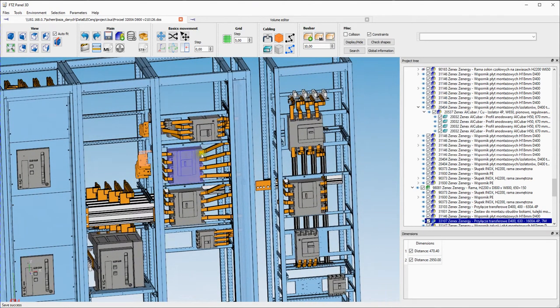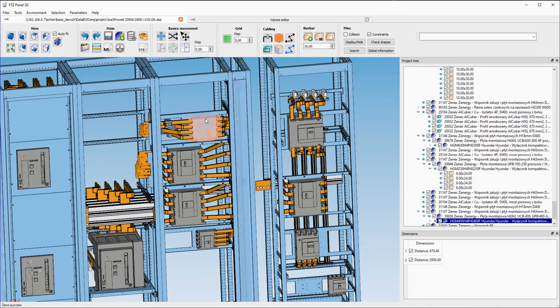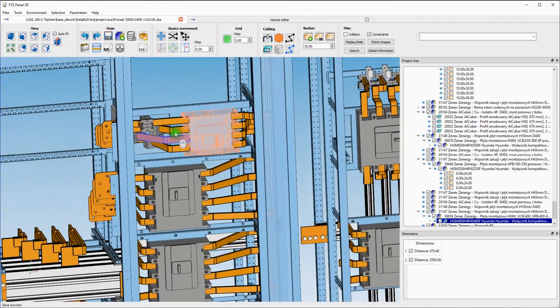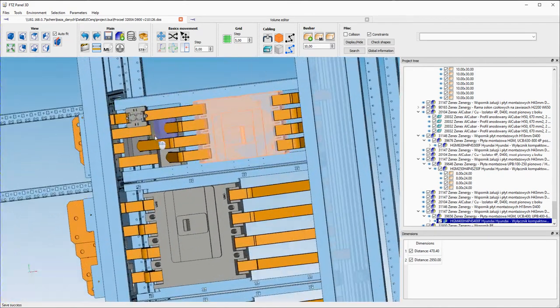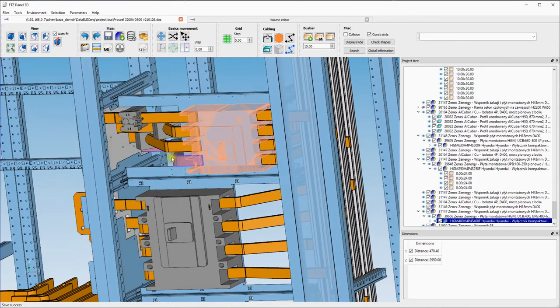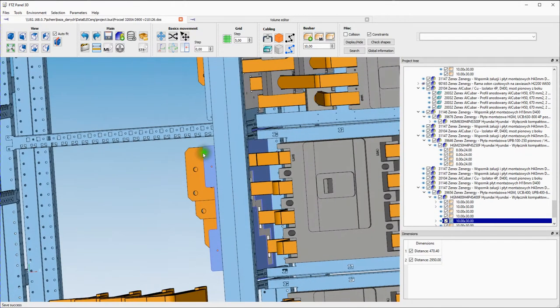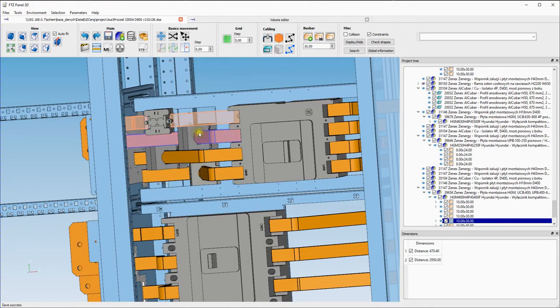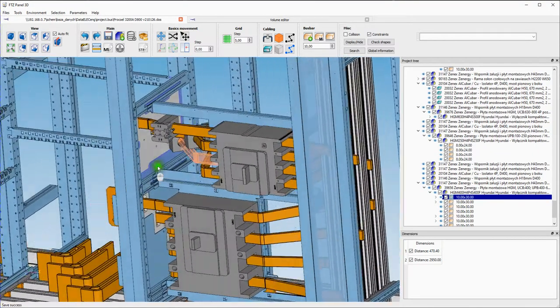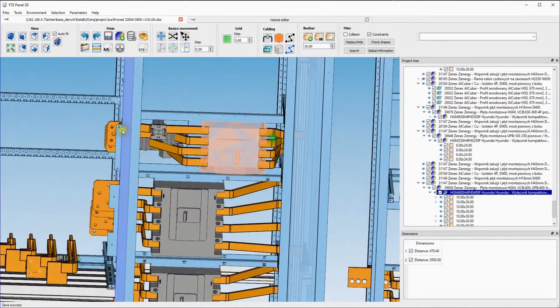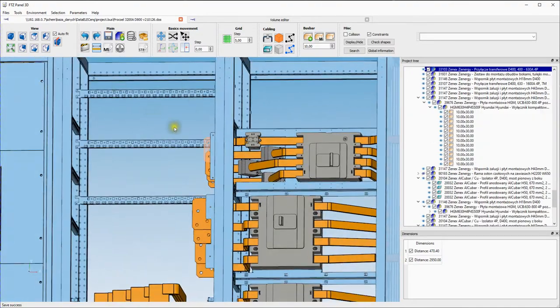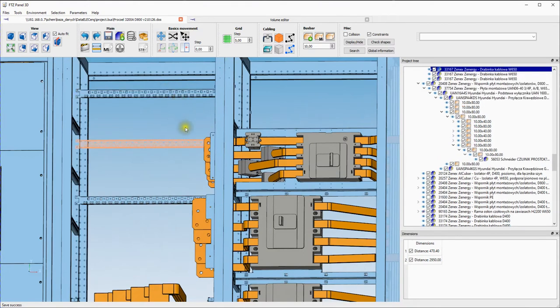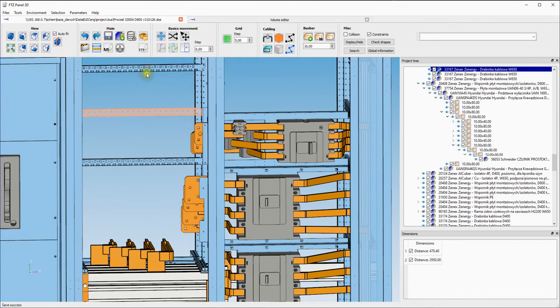Right, so this is the incoming going to the common bus bars. Here is also incoming 500 ampere to the bus bars, and outgoing you have one breaker, 400 amperes. Here there is some problem with the CT for the earth leakage, this RCBO, because there is no possibility to fit all those bus bars through one toroid current transformer. It's not enough space. So the toroid for this smaller breaker will have to be somewhere in the cable compartment, installed on the cable ladders with the cables.